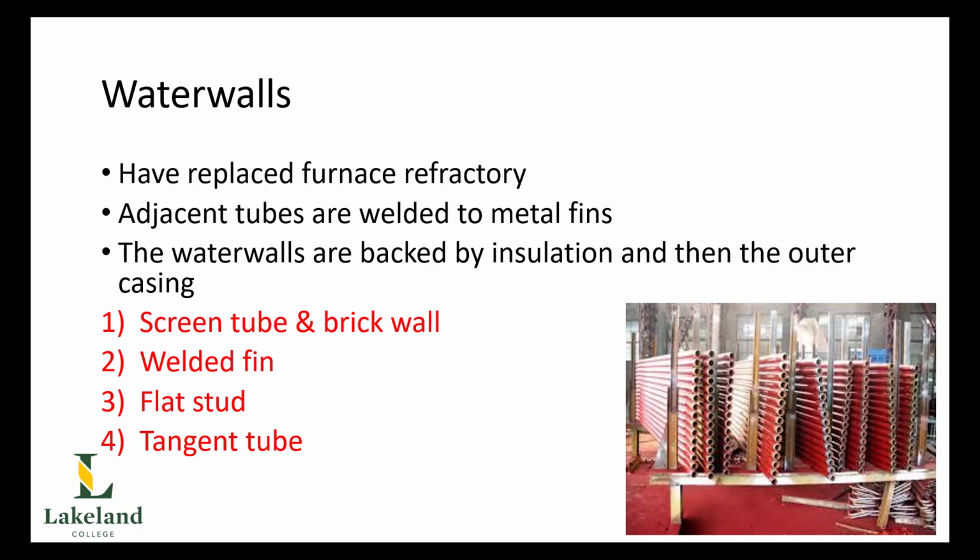water tube boiler. And this is done for a variety of reasons. Most notably, of course, to reduce refractory requirements, which will reduce the mass, also the maintenance required by the boiler, as well as increase the heat transfer surface area, which increases the rating and the overall efficiency of the boiler itself. Now, these tubes can be connected together in different ways, and we'll take a look at these here, as there are 4 different styles of water walls that we'll take a look at.